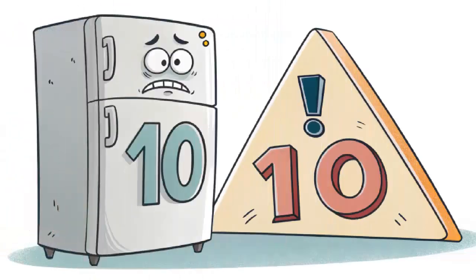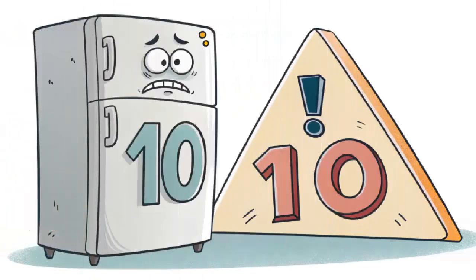1. Loose cable or connection. This causes intermittent voltage or current supply, which may shut off the compressor after it starts. Check all cable connections to ensure they are secure.